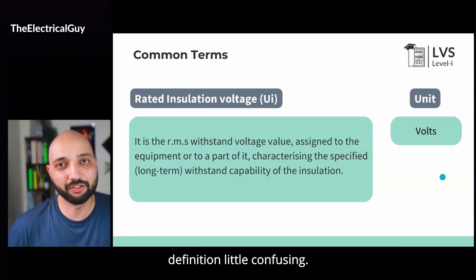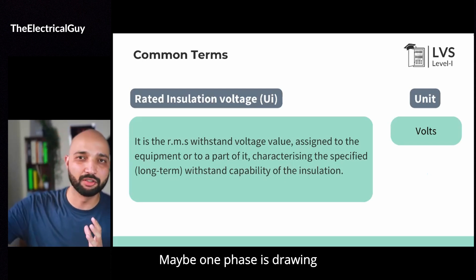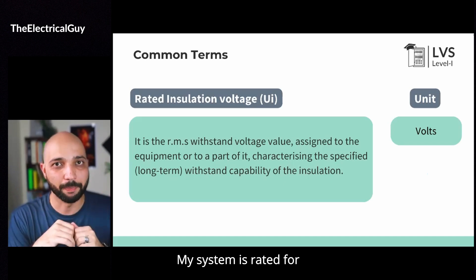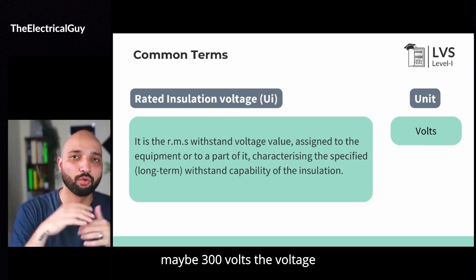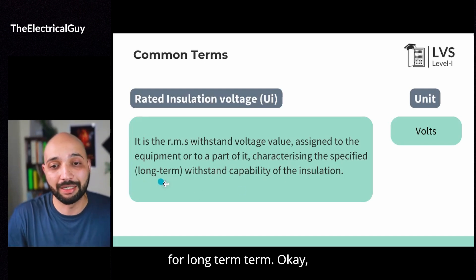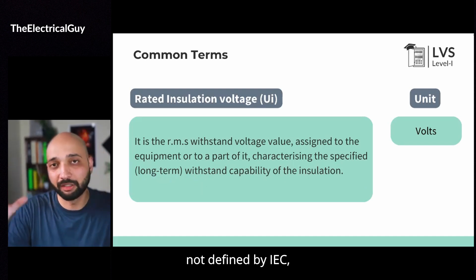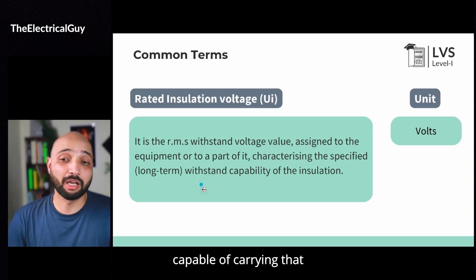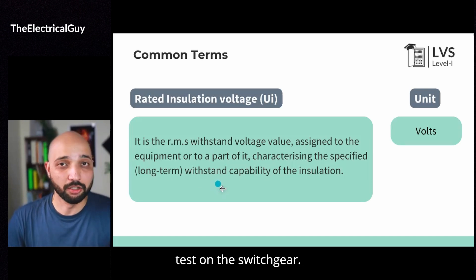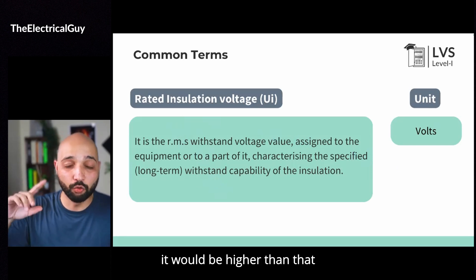Now you might find the definition a little confusing — I will simplify it. So there could be a situation where my system is imbalanced. Maybe one phase is drawing a huge lot of load, other two are not. In that case, there would be imbalance and maybe my system has to carry additional voltage for some time. My system is rated for let's say 230 volts, but because of this imbalance, maybe 300 volts of voltage imbalance is coming. In that scenario, my switchgear should be capable of carrying that voltage for long term. IEC does not specify whether long term means one hour, two hours, or three hours — that's not defined. But the switchgear must be capable of carrying that additional voltage for a long time, proven by conducting different tests on the switchgear. You will also find this parameter mentioned on the catalog or on the nameplate of the low voltage switchgear as rated insulation voltage, and it would be higher than the rated voltage.